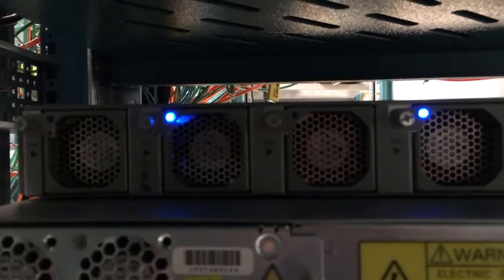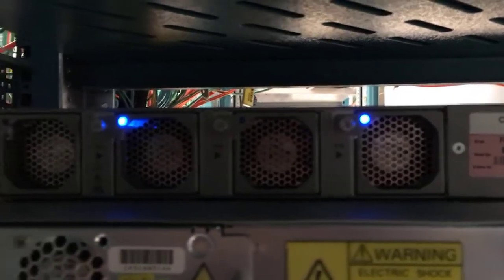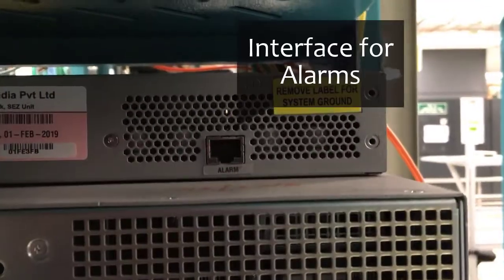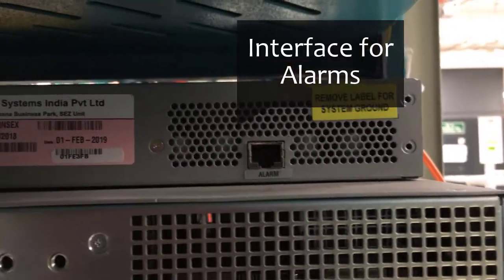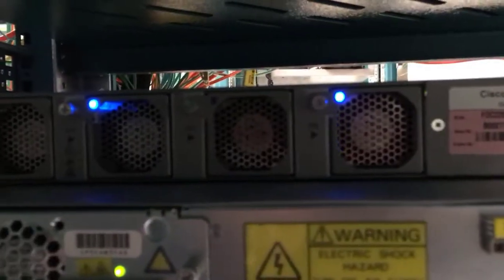In the back panel, we have 4 fans and an interface for alarms. The fans run in a 2+2 redundancy, that is, at most it requires 2 fans to be active. When the box is running at full capacity though, all 4 fans will be active and we use up to 270 watts of power in this case.